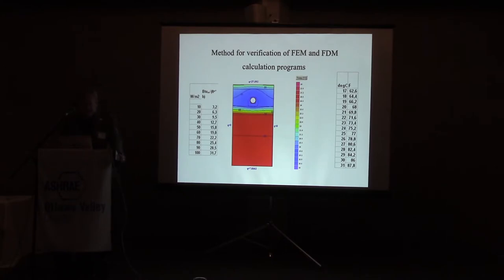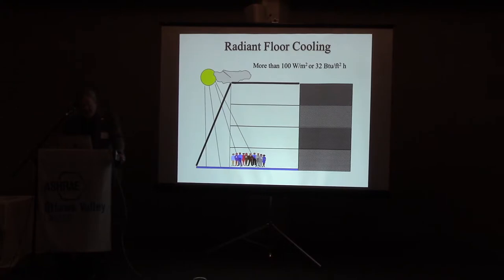to evaluate systems. So I talked about the floor cooling being limited to about 40 watts per square meter. But there's one exception. I'll show some project where that has been a big advantage. And that is if you have a lot of glass, like in a foyer, entrance hall, or an atrium, where you may have a lot of diffuse or direct sunshine on the floor, then you can remove more than 100 watts per square meter. So in these applications, the floor system is very efficient. Also for heating in the winter, because you get pretty uniform temperature distribution in these cases.